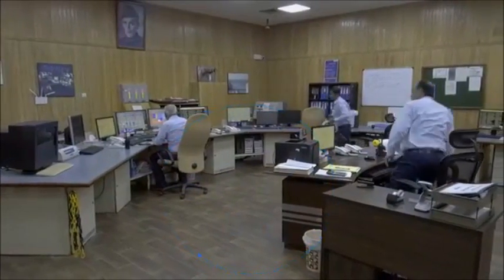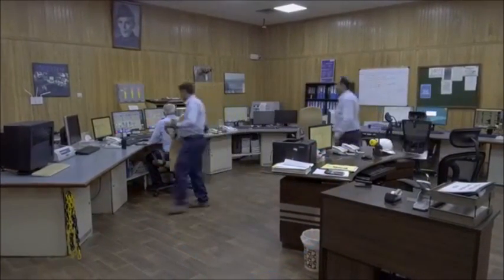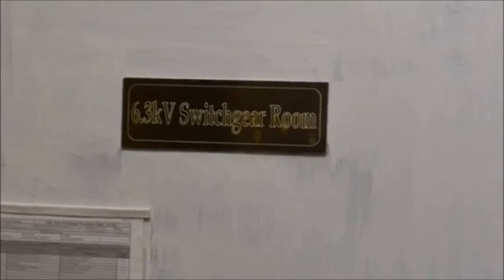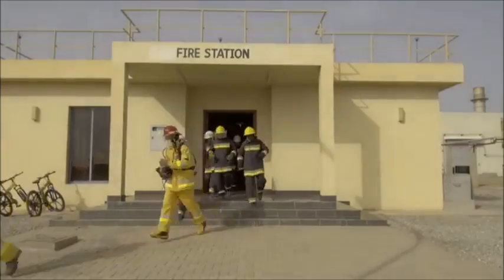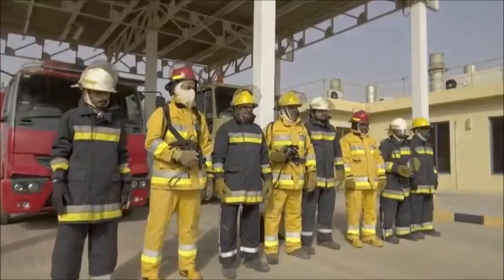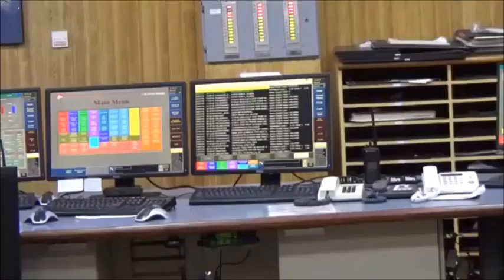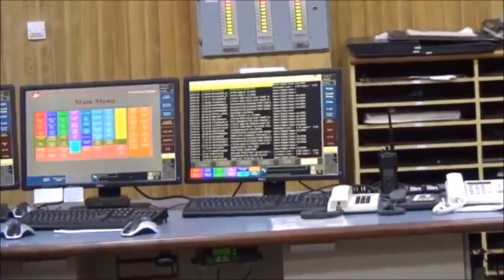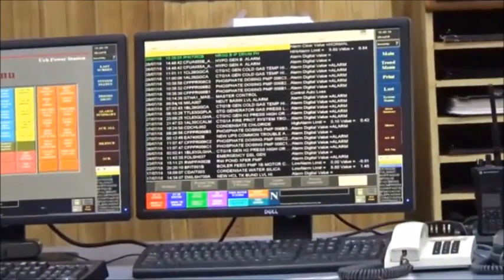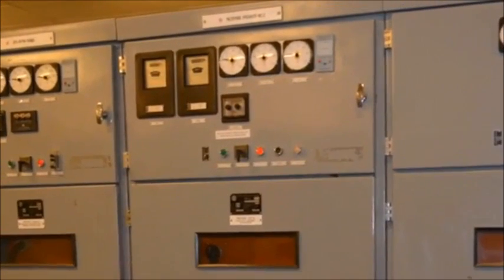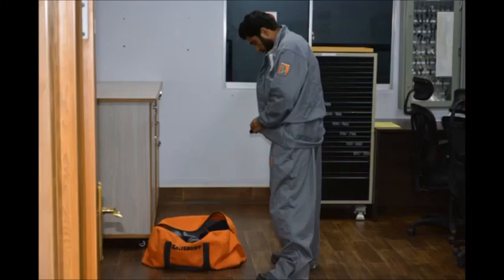The 6.3 kV breaker's room is located close to the control room. Keeping all his senses intact, the shift charge engineer immediately called the fire team and asked them to remain standby. After verifying all plant key parameters, the shift charge engineer called the fire team leader for sending a firefighter to inspect the room. The 6.3 kV room was partially filled with smoke. The smoke was dissipated through doors opening outside.